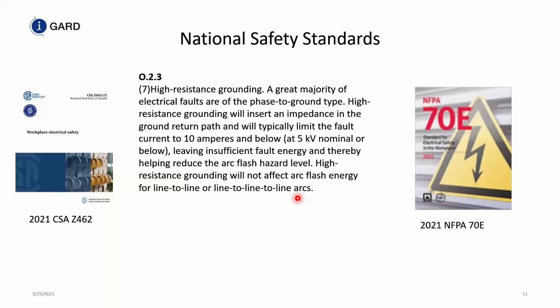So 7 of the electrical safety standards says a great majority of electrical faults are of the phase to ground type. High resistance ground, you will insert an impedance in the ground return path and will typically limit the fault current to 10 amperes or below on systems 5 kV or less, leaving insufficient energy and thereby help reduce the arc flash hazard level. Doesn't reduce the incident energy, but it reduces the arc flash hazard level. High resistance ground will not affect arc flash energy for line to line or line to line to line. Remember, when you do an incident energy study, you're going to be looking at the 3-phase bolted fault current that's available on that system. High resistance grounding does not change the magnitude of the 3-phase bolted fault current.